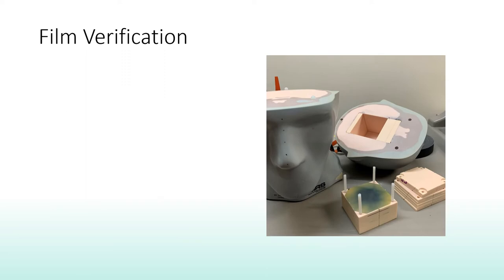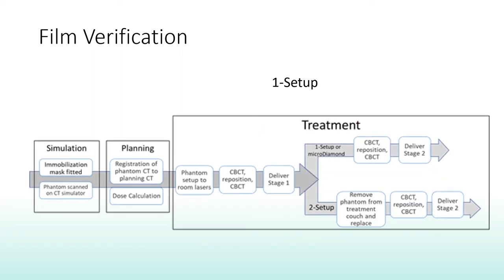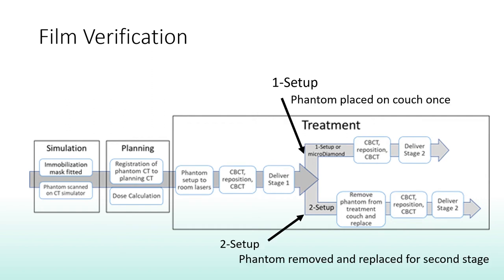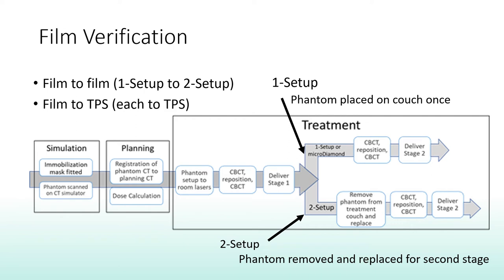Radiochromic film was used in two ways: to verify the treatment plan dose, and to assess the positional errors that could arise from setting up a patient twice for the second stage. This was done by exposing one film to both stages after one combined setup, and another film was set up twice by removing the phantom from the couch and starting the setup process again for the second stage. We did film comparison and gamma analysis for film-to-film and for each film to treatment planning dose.